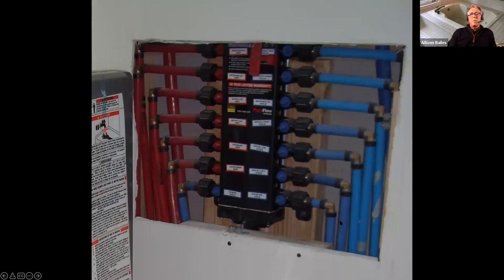Now this is a different manifold system, and this is an example of how not to do it. These 90-degree fittings are terrible. They go inside the pipe, which means you're reducing the diameter there. So not only do you have the 90-degree turn, but you reduce the diameter, which adds even more pressure drop right there. Much better is just to have continuous pipe and make a nice sweeping turn.